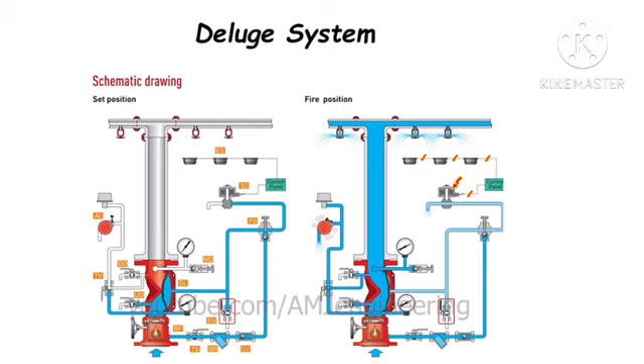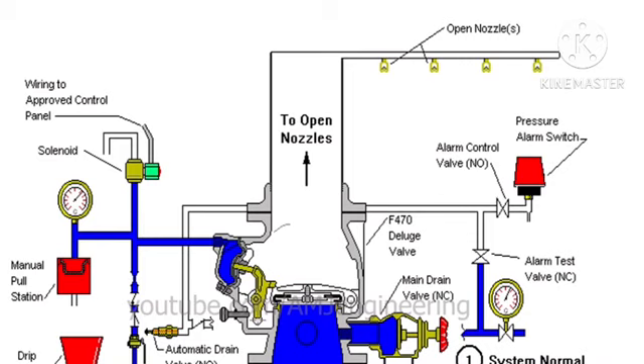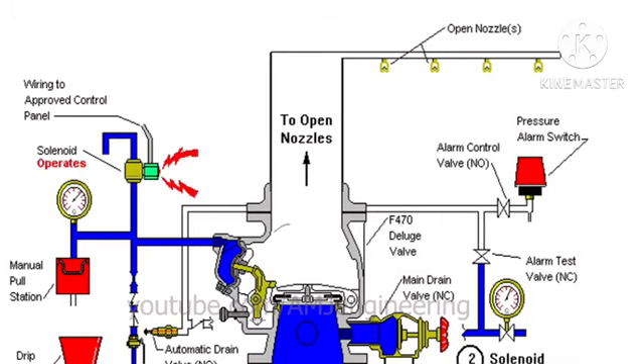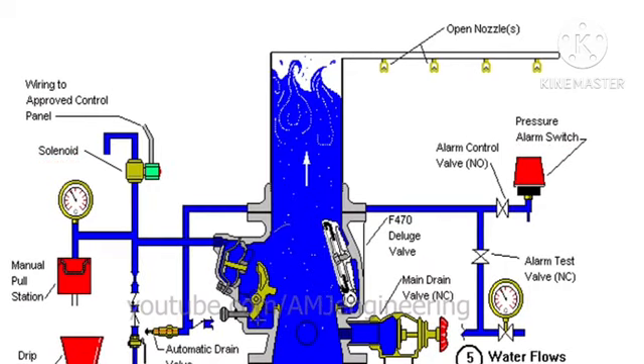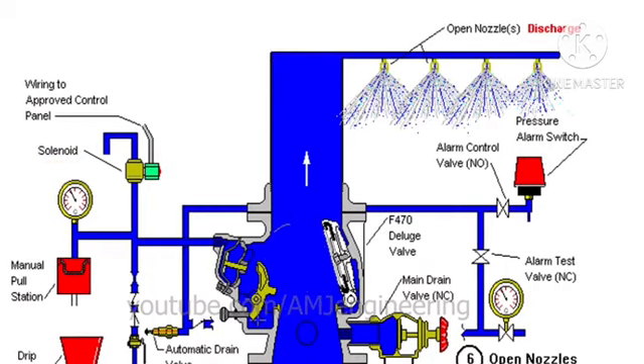Deluge systems are similar to pre-action systems in that they use another type of detection for operation. However, the biggest difference is that deluge systems use open sprinklers or nozzles. Instead of getting water flow from individual heads that have operated, once water fills the system, water will flow from every sprinkler head. Much like a pre-action system, a deluge valve will keep water from filling the system until the operation of another type of detection system, such as smoke detection. Once the detection system is activated, water not only fills the system, but flows from the open sprinklers or nozzles.